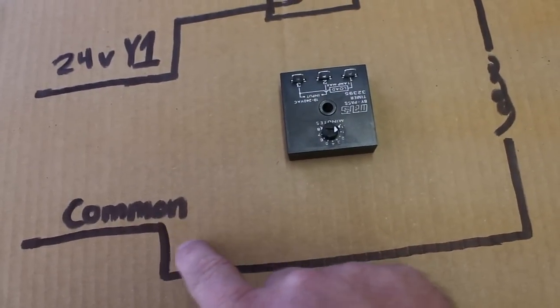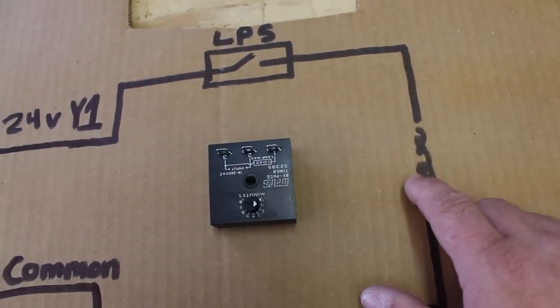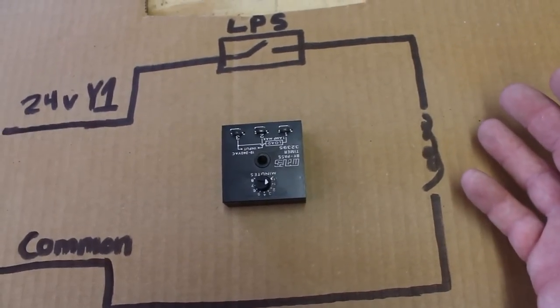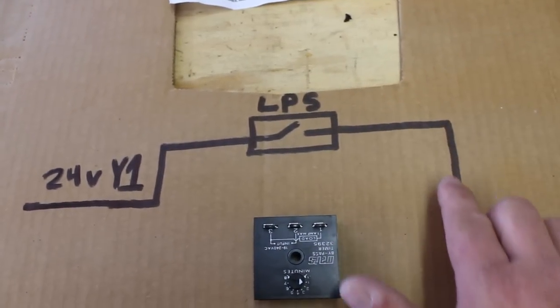We have our common wire running around to one side. This is the contactor coil in this particular case, but could be a coil for any relay depending on your application. We have Y1 going here to the low pressure switch then coming out.